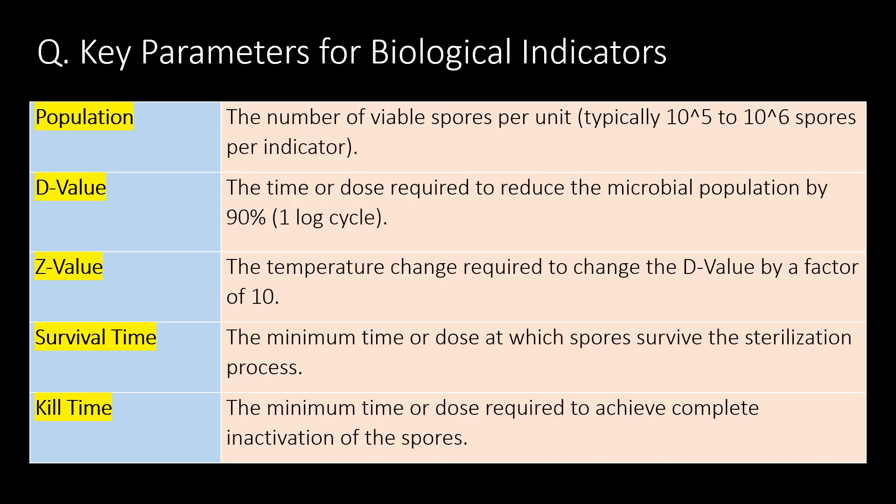What are the key parameters for biological indicators? Referring to a table for key parameters and their descriptions, the key parameters for biological indicators are: overall population, D-value, Z-value, survival time, and kill time.